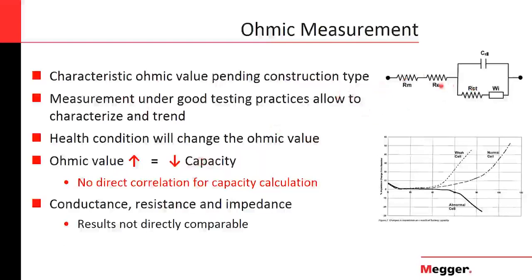We can see it here to the right of the slide. And if you measure across the terminals of this circuit, of course, you're going to get an ohmic value. It's mentioned in the standard as ohmic value because that will depend on how you measure it. Any method you use to measure it, if you measure under good testing practices, will allow you to characterize this battery or this cell, and will allow you to trend the value.